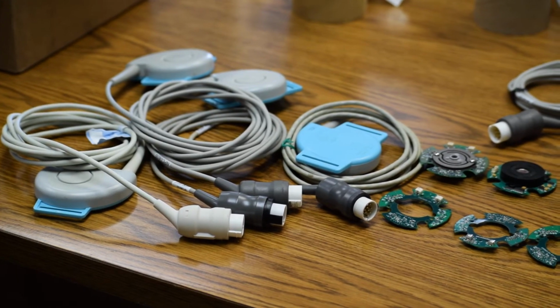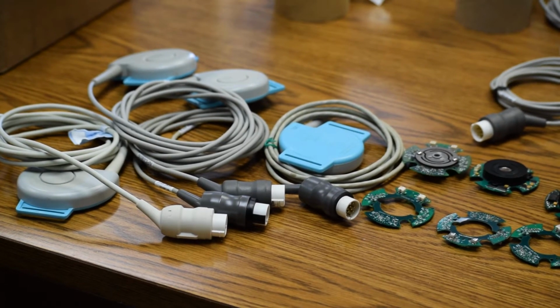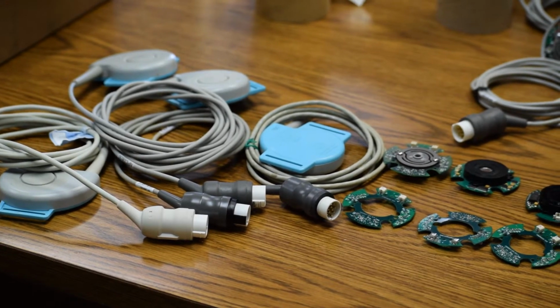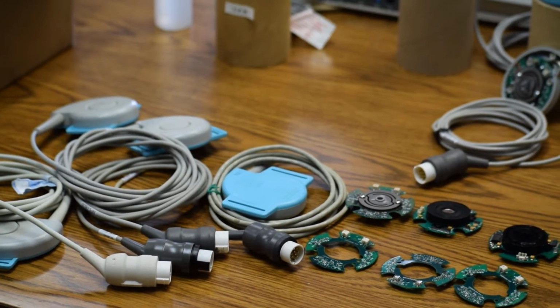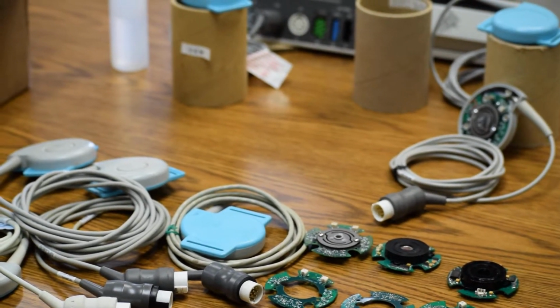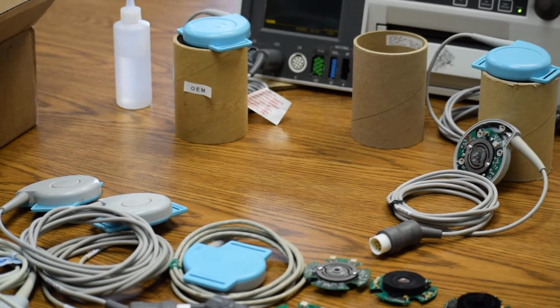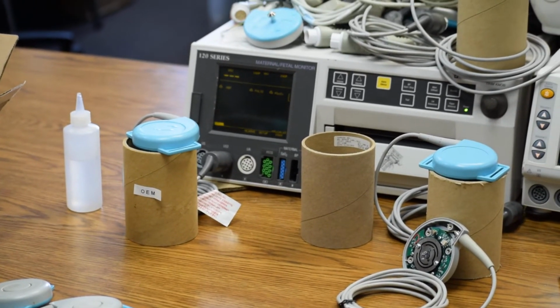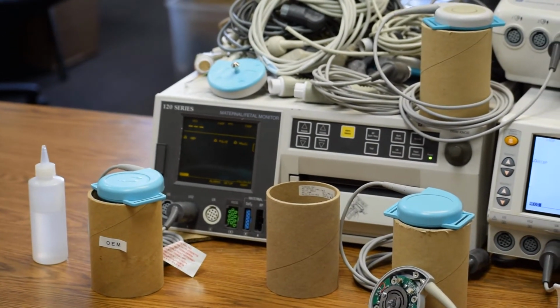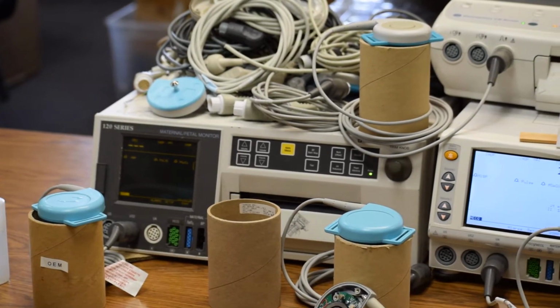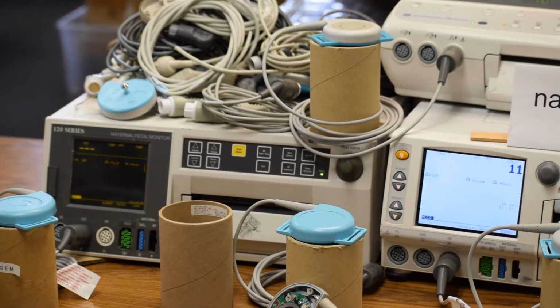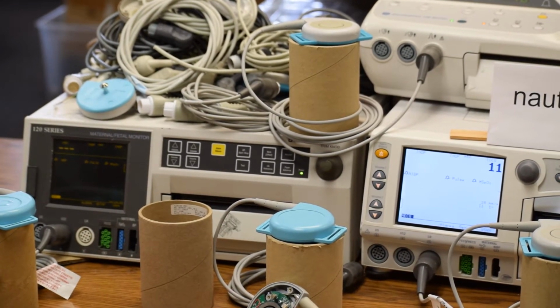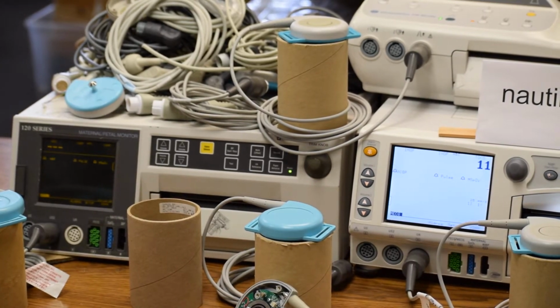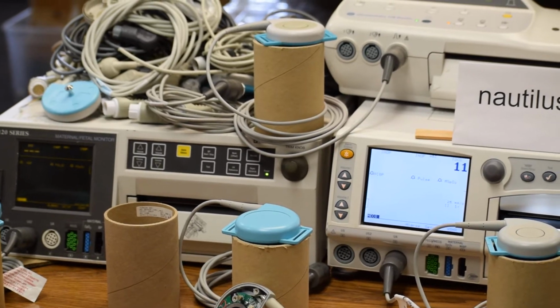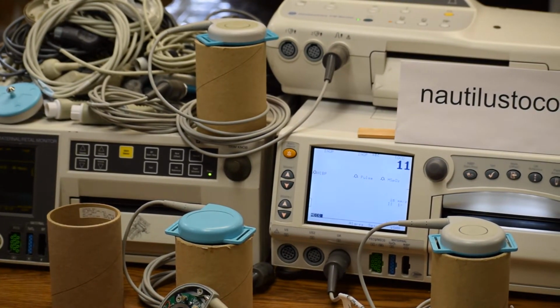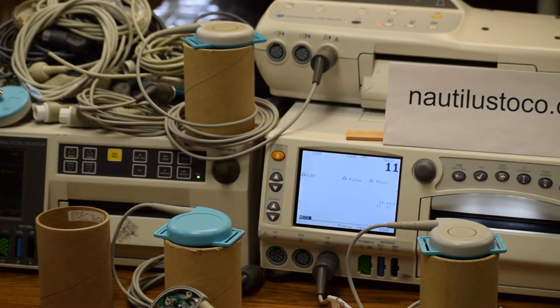PEEK stands for polyether ether ketone. Precision engineering work, tooling, high performance resin and material means the cost will be significantly higher compared to what GE charges, especially when a third party company has to run production batches of few thousand units at a time. Cost of the PEEK material is more than 100 times higher compared to generic plastic polymers used for molded connectors, and it is extremely difficult for the injection mold process, adding to the cost factor. These generic molded cable connector assemblies cost in the range of $10 per unit for low volume batch production, whereas a single connector in PEEK material will cost more than $120 each on average.